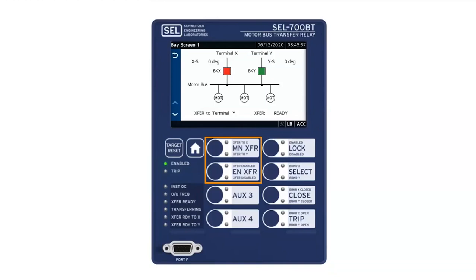There are also cases where you might not want to do a residual transfer. One of the reasons to do a fast transfer or an in-phase transfer is that you conserve all the energy that's on the spinning machines. But if you go to a residual transfer, maybe the machines lost too much speed, and then if you reconnect them, you have a very high rush current from all the motors speeding up, getting back to speed again, and that may not be possible. So you have to choose what to do in those cases, and that depends on the installation.